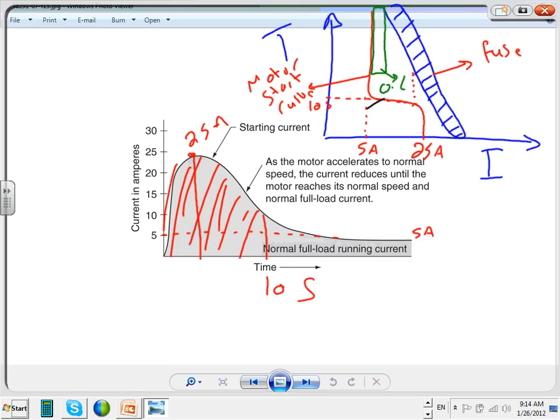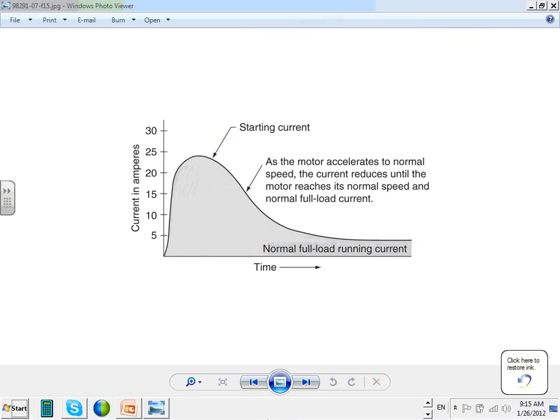And the starting current, I like to do that. This area here is the area that the current is going to be starting. You're giving me a certain amount of amps for a certain amount of time to start the motor. You exceed this one, you're doomed if you don't have a fuse. Any questions, guys, about this? Any comments, any questions about the starting? Almost always the start current is 6 to 10 times. We have tables in the code that we calculated the start current based on that one, guys.